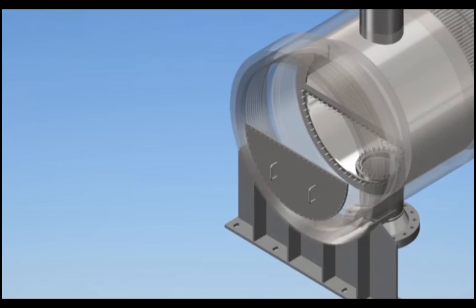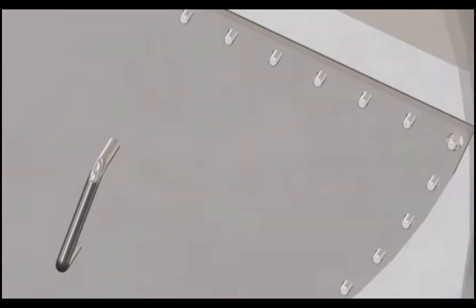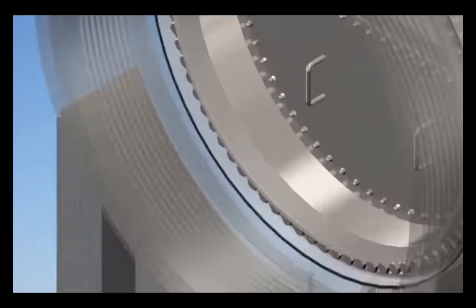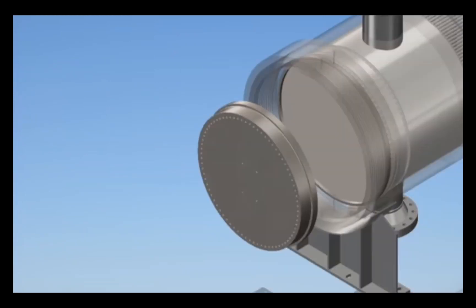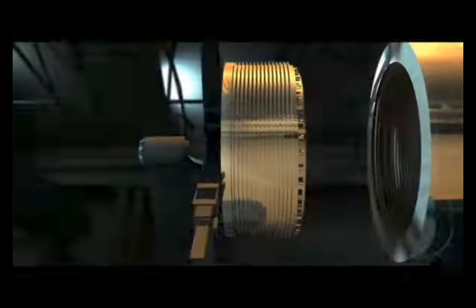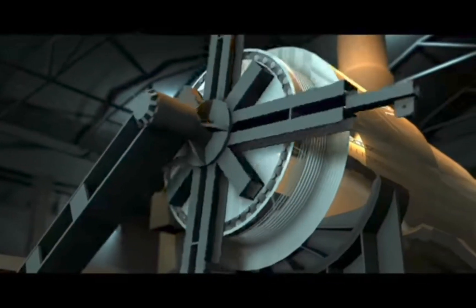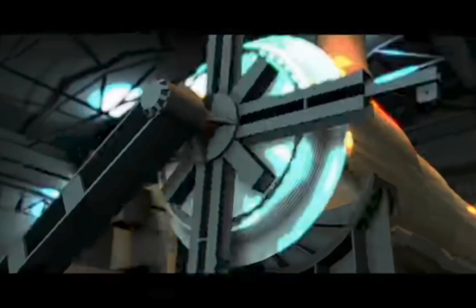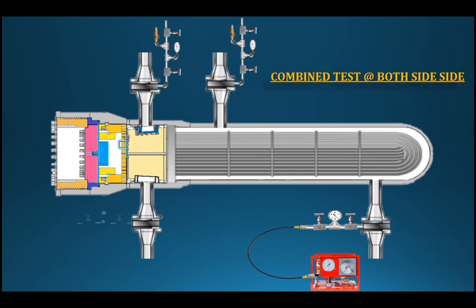The partition cover is fixed. The diaphragm plate is fixed in position, and the gasket is cleaned and placed in the correct position. The full pressure configuration is set. The threaded ring and channel plate are fixed. The compound test is then performed with both the shell side and tube side pressurized simultaneously.